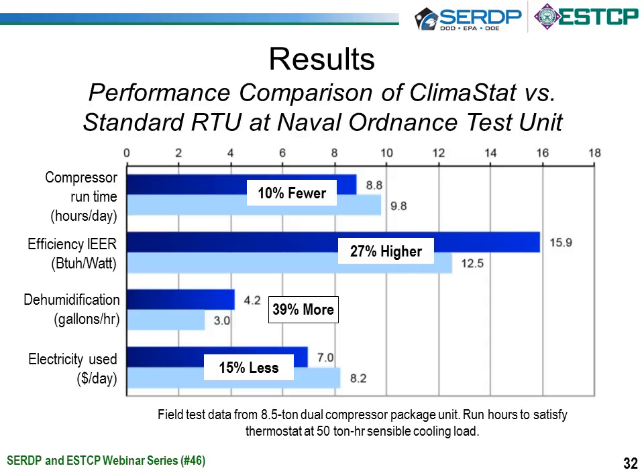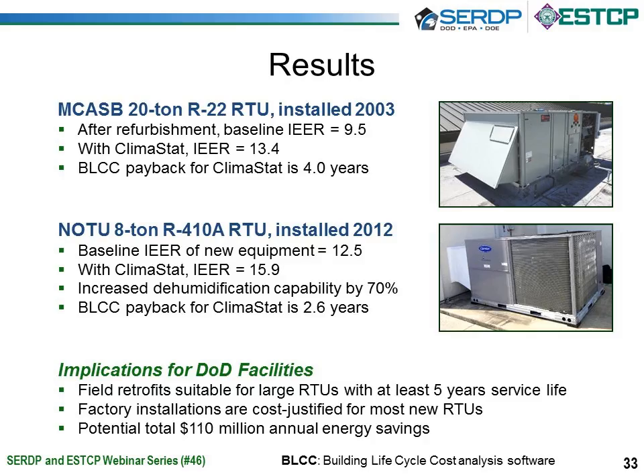To summarize from the Naval Ordnance Test Unit in California, we had 10% fewer compressor runtime, 27% higher efficiency, 39% more dehumidification, and 15% less electricity. So at the South Carolina site, the efficiency went from a 9.5 to a 13.4, giving a payback period of 4 years for that site. At Cape Canaveral Air Force Station, NOTU in Florida, it went from a 12.5 IEER to a 15.9. Dehumidification capabilities increased significantly, and the payback was 2.6 years.